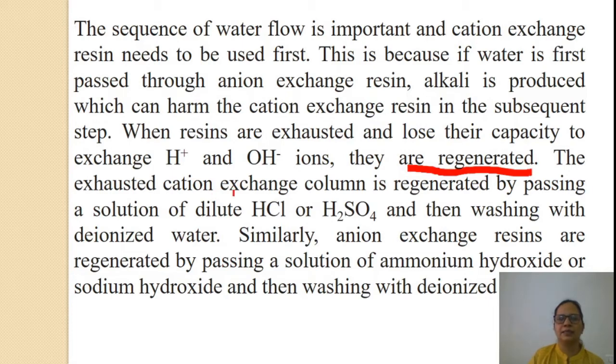The exhausted cation exchange column is recharged by passing a solution of dilute hydrochloric acid or sulfuric acid and then washing with deionized water. Similarly, anion exchange resins are regenerated by passing a solution of ammonium hydroxide or sodium hydroxide and then washing with deionized water.